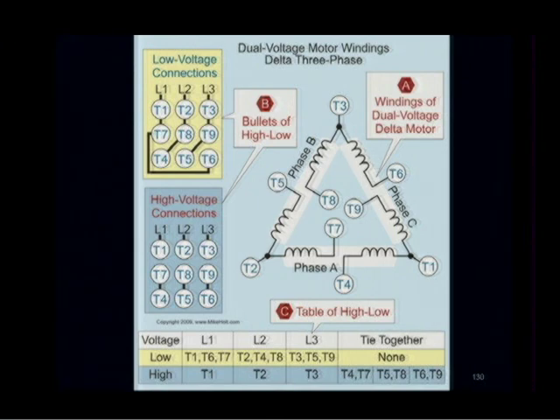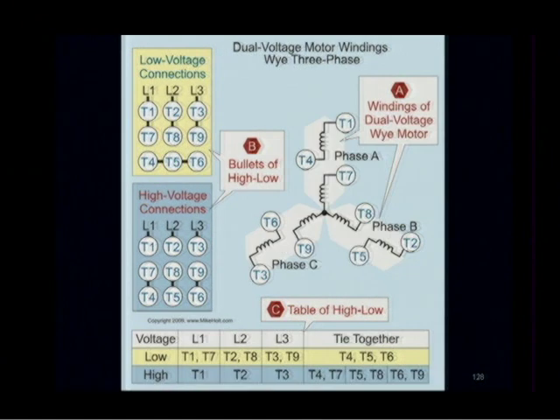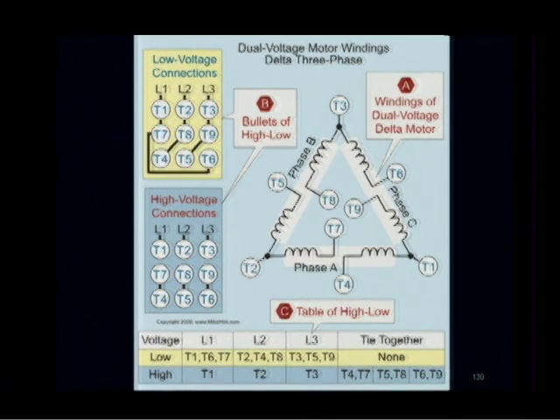Help me out, guys. Why do I have a Y configured motor, and why do I have a delta configured motor if we still have 230, 480? Anybody know the differences and why? It's not real important whether you have the Y or delta, it's just the construction characteristics of the motor, unless you use the Y start delta run for a reduced voltage start. Okay, so if you're an electrician, it doesn't really matter because the nameplate on this motor is going to show you a different set of connection leads.